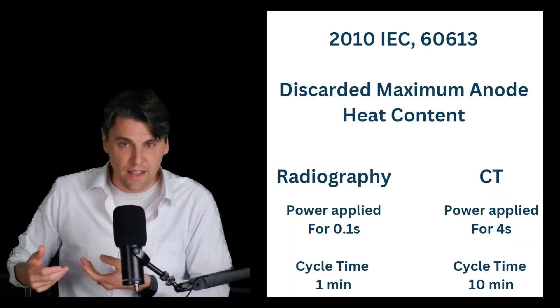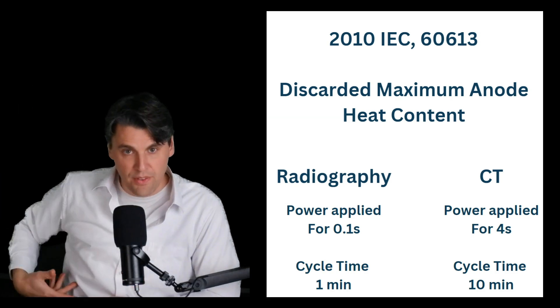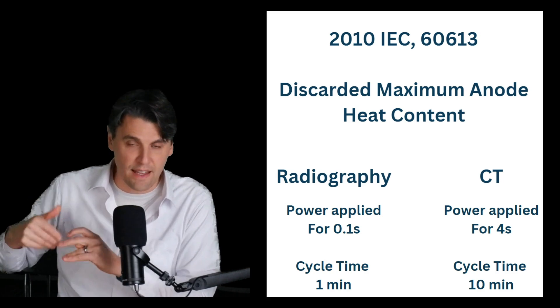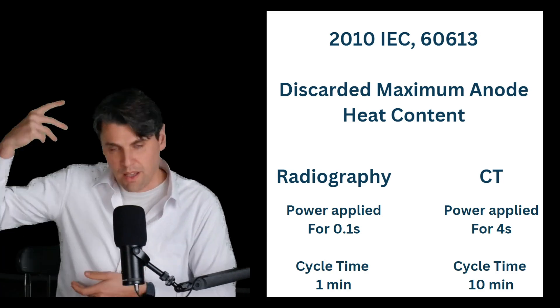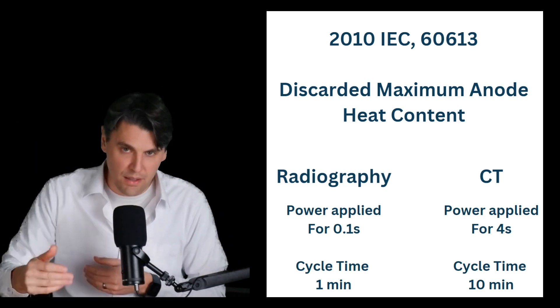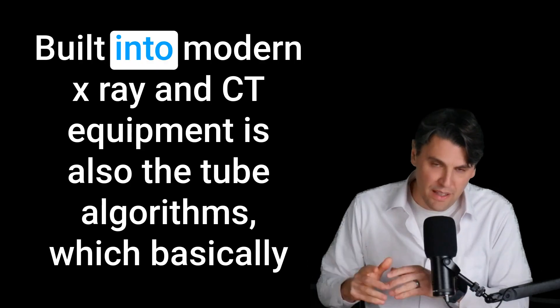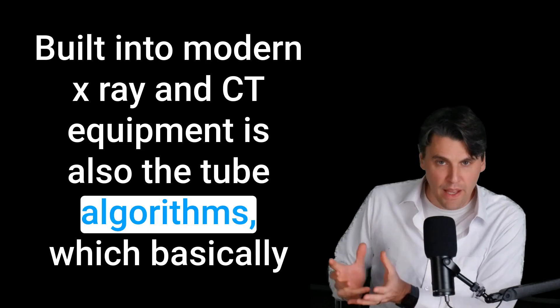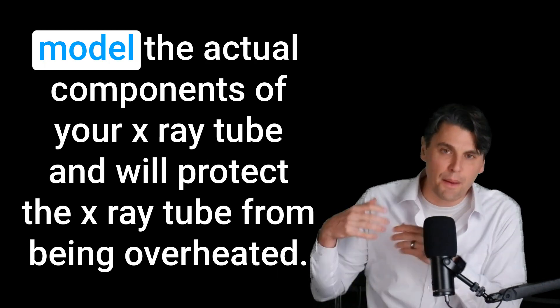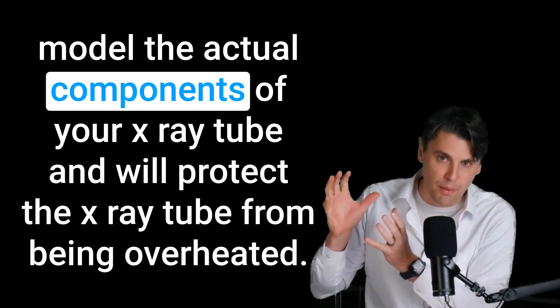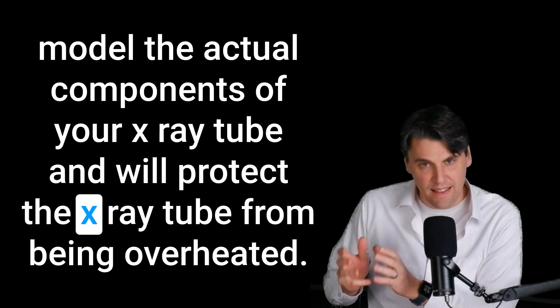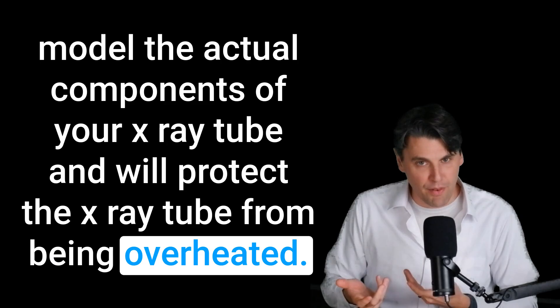The basic mode is also designed for CT. In this case, you assume you're going to take a four-second scan and then wait 10 minutes before the next patient scan. Built into modern x-ray and CT equipment are tube algorithms which basically model the actual components of your x-ray tube and will protect the x-ray tube from being overheated.